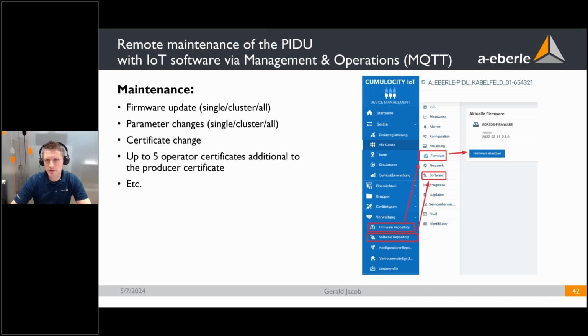Some additional features. I don't want to go too much into detail, but one big difference one has to be aware of is that we have our own software called AE Toolbox. With AE Toolbox, we do the parameter setups, and we have an export functionality. With this export functionality, a zip file comes out of our own software. This zip file holds the complete parameter setup with earth fault parameters, SCADA parameters, PLCs, so PLC functionality, and so on. This is all stored in one zip file, and this zip file can then be sent out to all the different devices connected to the Cumulocity IoT. So we only send complete zip files via this central IoT software.